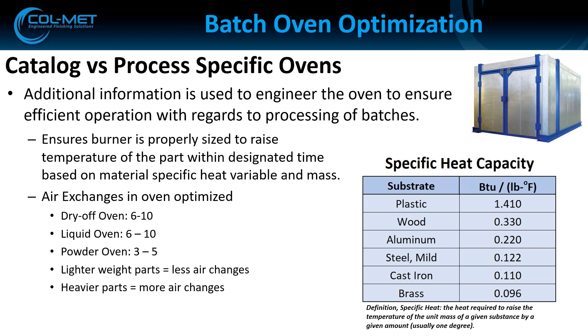Our catalog ovens are typically designed at 6 air changes, but if we know you'll be curing powder, we can run it through our calculator and design the oven specifically for your needs. If you have lighter weight parts that may blow around, that points us in a certain direction, or if you have heavier parts, that allows for more air changes. By knowing these specific details, we can design an oven that operates efficiently and uses less energy overall.